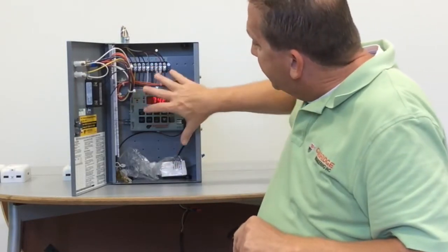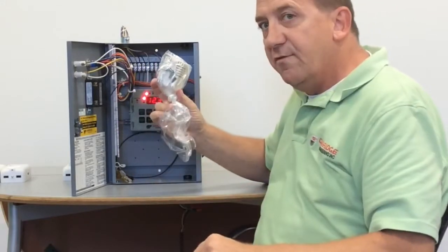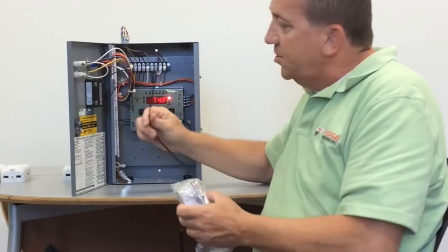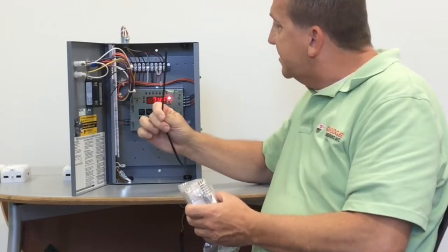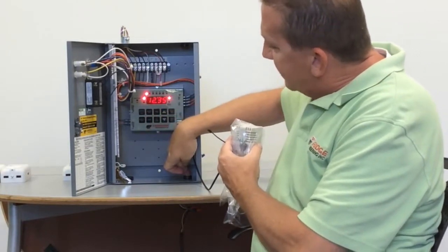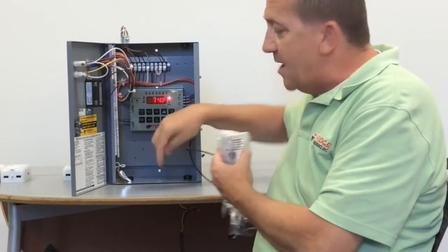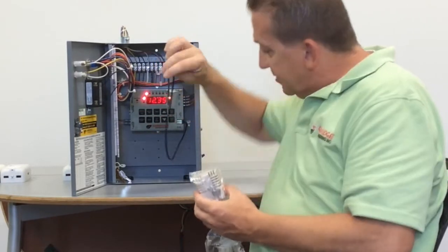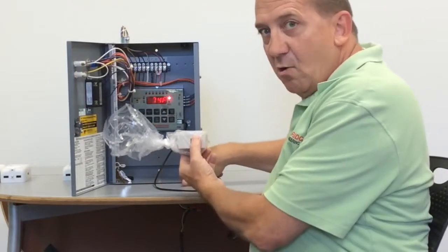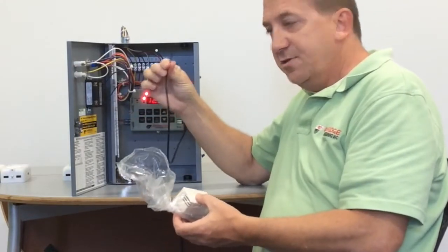You also are going to get your thermostat. Inside here is what we call our SH-1 cover. This is basically the cover that encompasses and protects your thermistor. So when this gets installed, there's two knockouts on top and two knockouts on the bottom. Typically, they pop the knockout on the bottom of the can out. They put this thermistor out that hole and they install the cover in line with that hole. So once again, this must be installed to protect your thermistor.